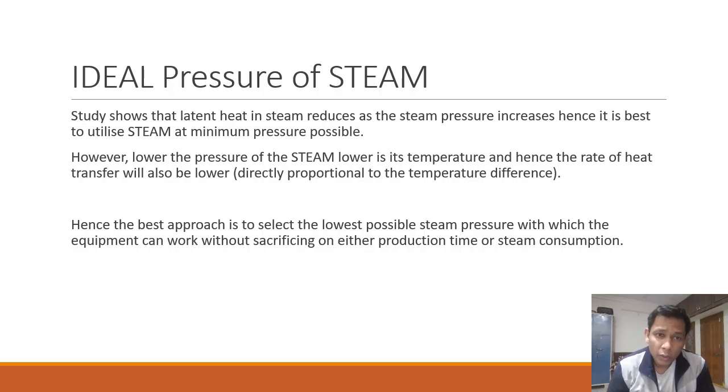But you cannot decrease the pressure to a very low value, because the lower the pressure of the steam, the lower is its temperature, and hence the temperature difference between the product and the source will become smaller and smaller, and the amount of heat transfer will be lesser. So the best approach is to select the lowest possible steam pressure with which your equipment can work without sacrificing either production time or steam consumption.